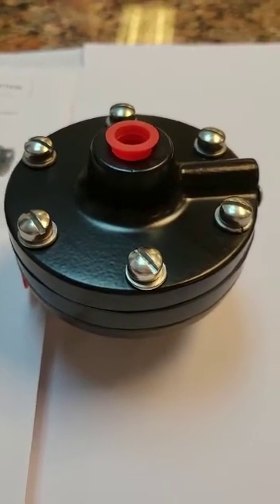You can see — looking at the connections, this arrow from left to right — the pressure inlet, signal output, signal inlet. And it can be surface mounted close to the positioner. The air supply is around 20 to 30 PSI, and the output here is also controlled to match with the inlet.